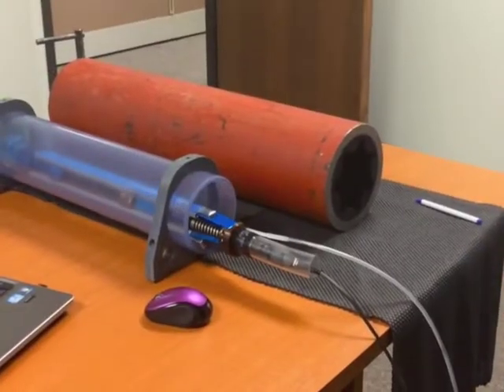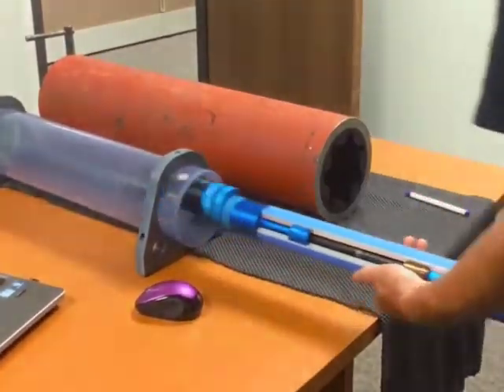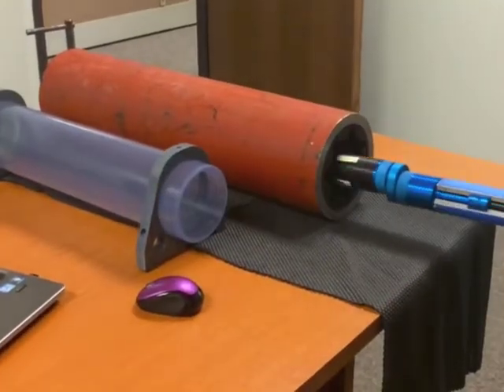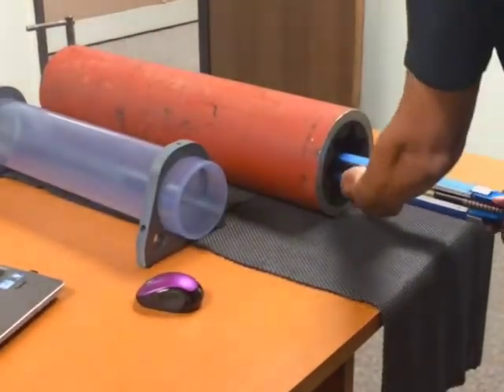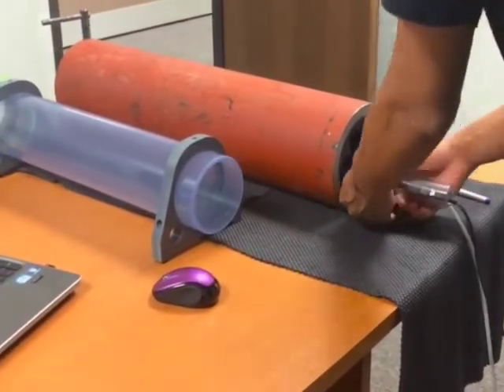As a simulation for a stator, we insert the probe into a stator sample, and the process is repeated for measurement instead of calibration.